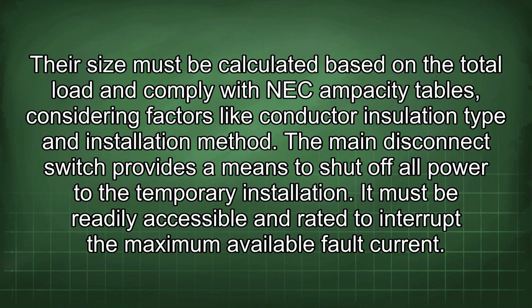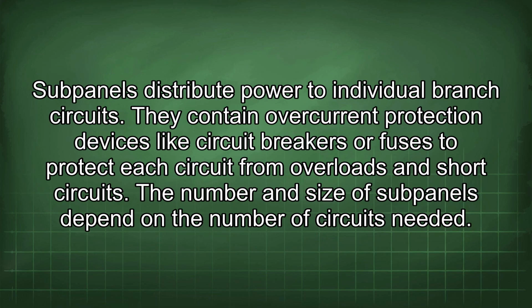The main disconnect switch provides a means to shut off all power to the temporary installation. It must be readily accessible and rated to interrupt the maximum available fault current. Subpanels distribute power to individual branch circuits. They contain overcurrent protection devices like circuit breakers or fuses to protect each circuit from overloads and short circuits. The number and size of subpanels depend on the number of circuits needed.